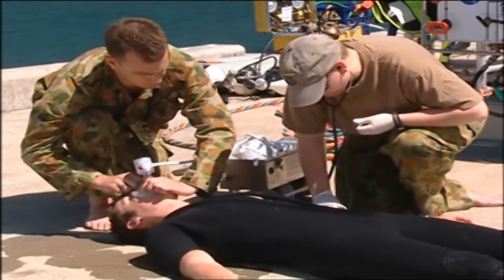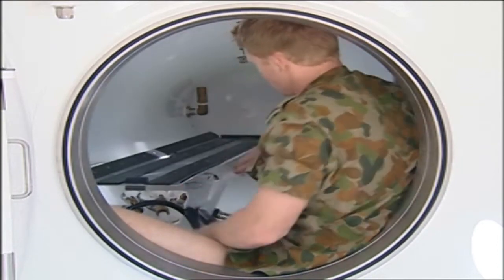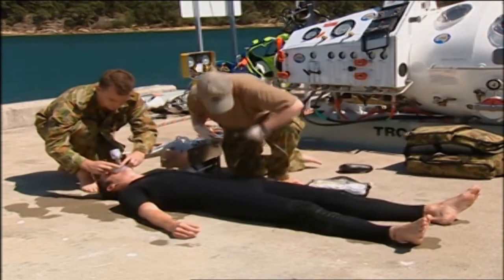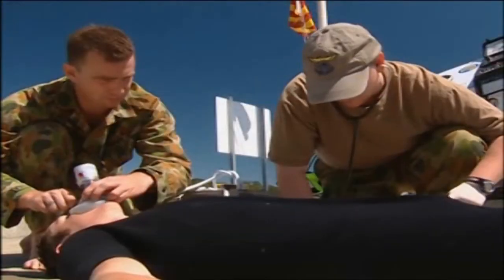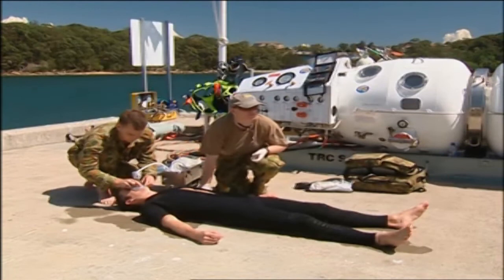The chamber can also be used to treat divers who are suffering from a range of diving-related medical conditions. To set the chamber up for the treatment of an unconscious diver, unclip the stretcher support in the RCC and pull it across to the centre of the chamber. Then fit the removable slide rail in the transfer lock. In this scenario, an unconscious diver has suffered medical complications several minutes after completing a dive. A specialist trained in underwater medicine assesses the patient and a hyperbaric doctor is also consulted. In this case, the medical team determines that therapeutic treatment is required.